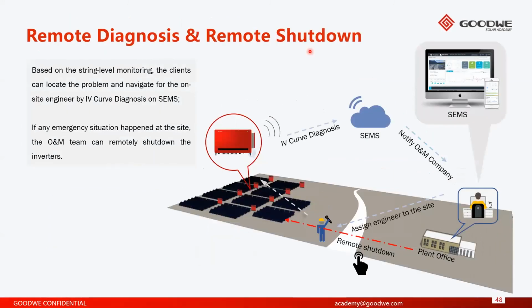So this allows a remote diagnosis of the PV plant, and we also have the ability to have a remote shutdown. This remote shutdown is becoming important in Europe, which allows a third party such as a grid operator to shut the PV plant down or shut certain sections of the PV array down under a variety of reasons.